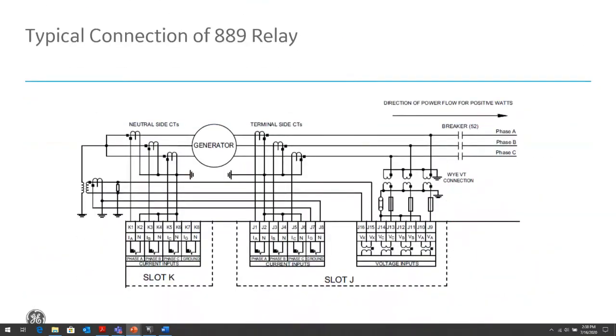This is a typical connection of the 889 series generator differential relay. And you can see the CTs on the generator neutral terminals. The polarity of those CTs is connected to the polarity side of the relay, whereas on the terminal side of the generator, it's the opposite. And that's where that 180 degrees comes in. The reason we have to do that is for metering purposes, because we need to measure the flow of power into the power system, so we can measure positive watts into the power system. So we need to connect the CTs in this configuration to measure the right flow of power, but it causes an issue with our differential, so we need to correct for that 180 degree shift.